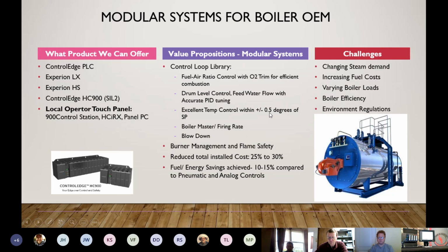Kind of depends on your final control elements and how well they're calibrated and able to do the control. But if everything is on point and you have really good final control devices as well, you can achieve pretty tight control. Boiler master, so you can set up boiler master in the HC900, and then the last one is blowdown. Some of the challenges that the HC900 addresses for boiler type applications, if you have changing steam demand, the HC900 can do a lot of predictive type control in the configuration to be able to adapt to the steam demand changes. It also helps reduce some of the fuel costs using the fuel air ratio.